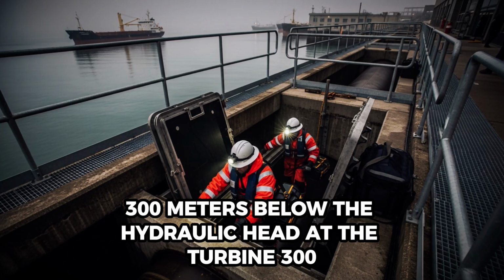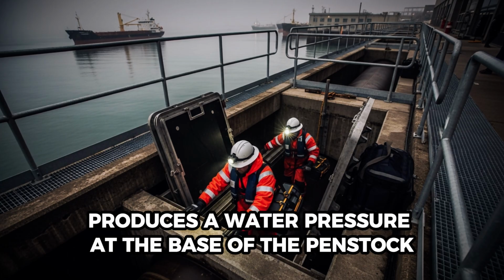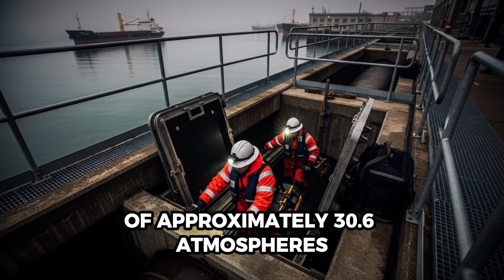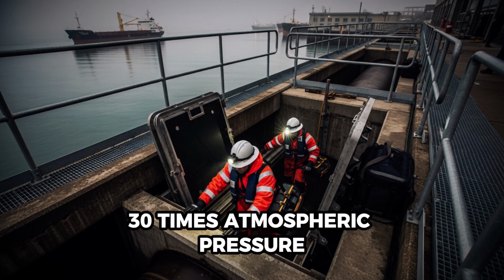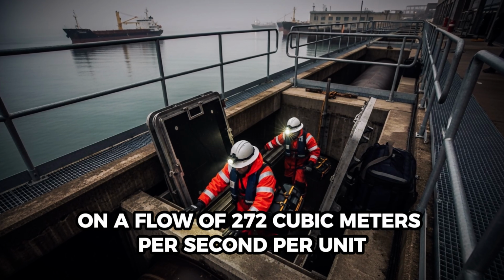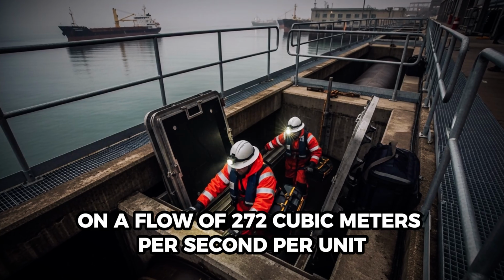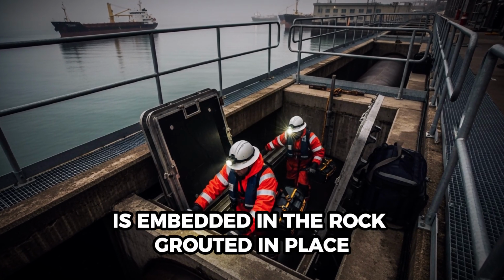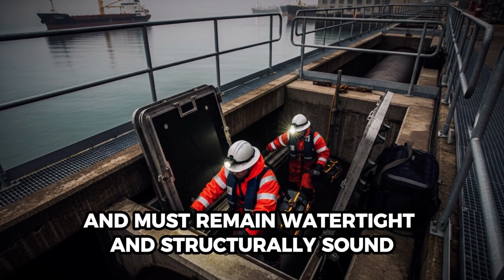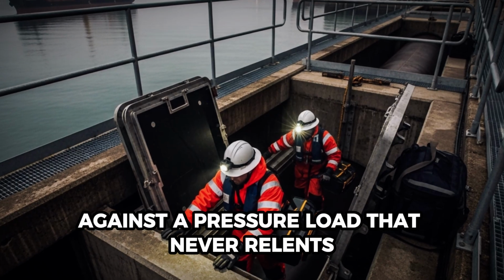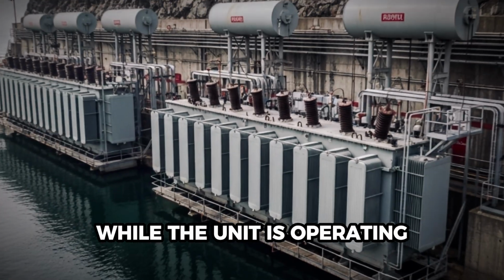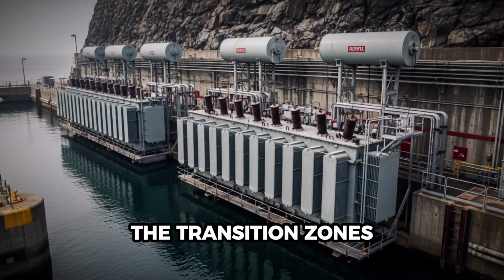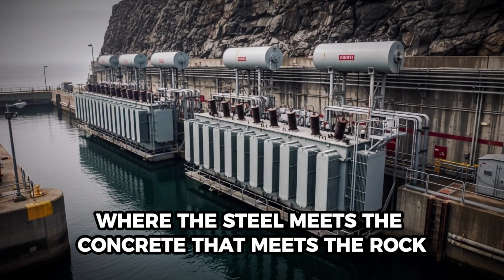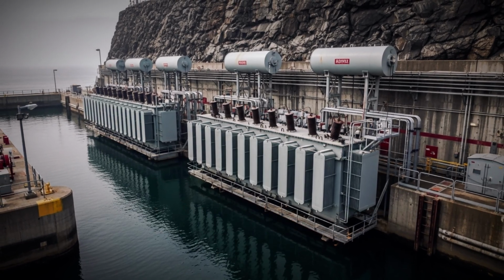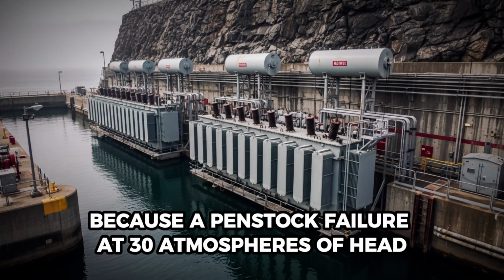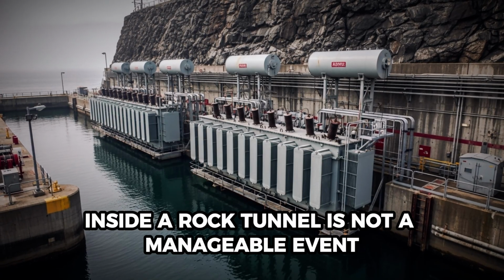The hydraulic head at the turbine, 312 meters, produces a water pressure at the base of the penstock of approximately 30.6 atmospheres, 30 times atmospheric pressure, on a flow of 272 cubic meters per second per unit. The steel lining that contains this flow is embedded in the rock, grouted in place, and must remain watertight and structurally sound against a pressure load that never relents while the unit is operating. The welded seams in this lining, and the transition zones where the steel meets the concrete that meets the rock, are inspected on every unit outage. Because a penstock failure at 30 atmospheres of head inside a rock tunnel is not a manageable event.